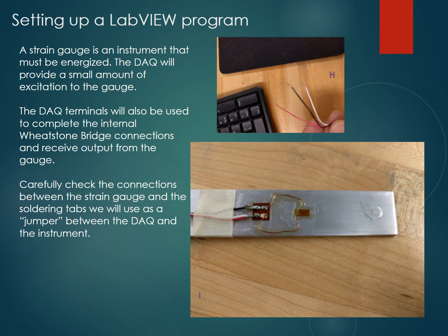And you can see them down here in Figure I, where they connect into the soldering tabs that link up to the strain gauge. Of course, you can almost see the circuit here. The black wire would contain the excitation or the power-up voltage. That would then go to the strain gauge, and from there, the electricity would then flow out of the gauge to the red and white wires. Of course, the red wire will be our signal output. The white wire will provide completion with the Wheatstone bridge that was previously mentioned.